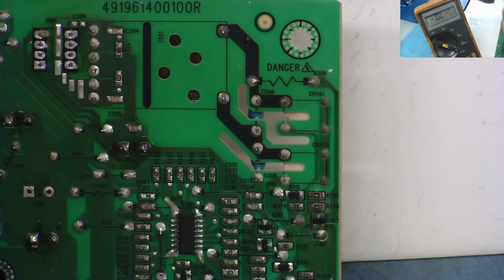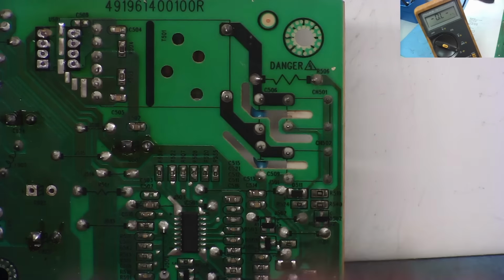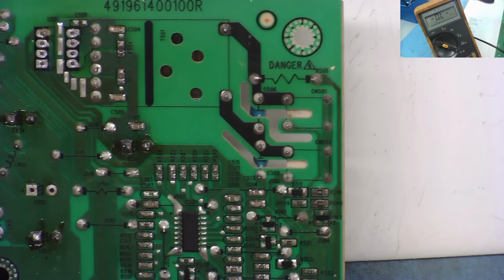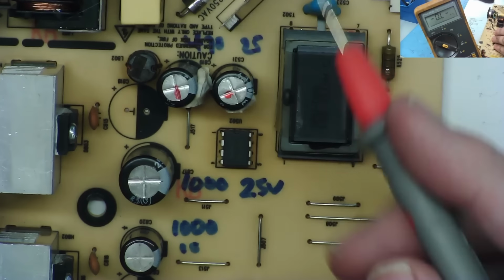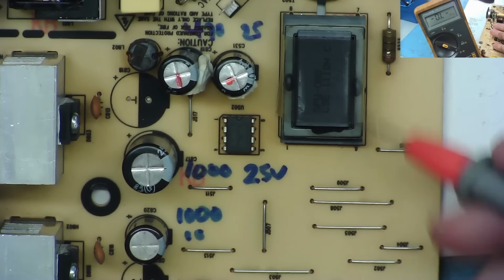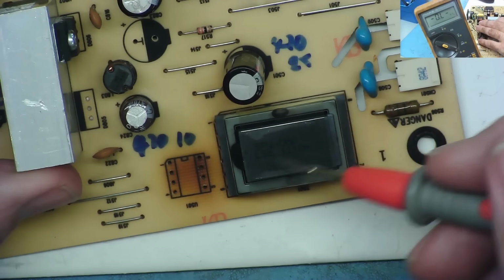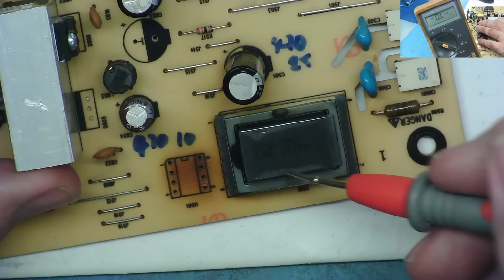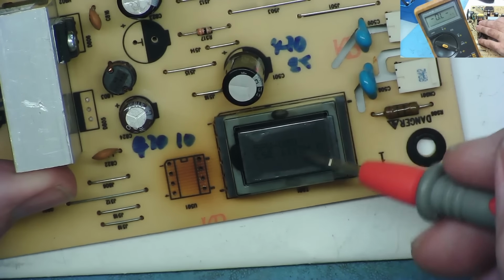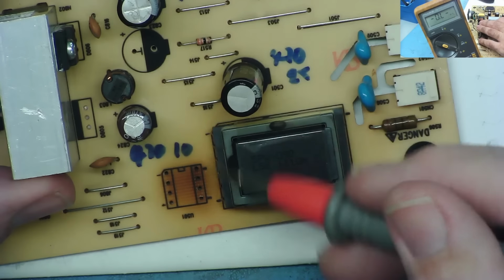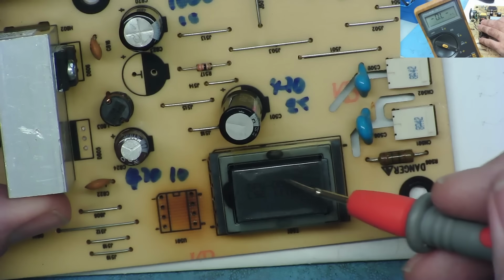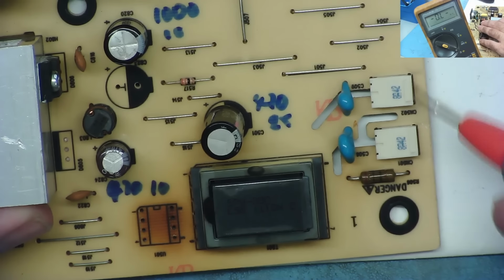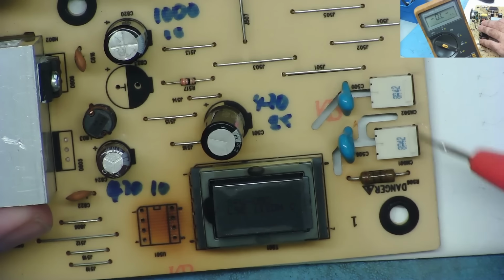We could use the low ohms meter, but I'm pretty confident that both of these transformers are okay. And the other reason, apart from the fact they read basically the same as each other, is that if you've got a shorted turn or something in one of these, the thing is going to look distressed - it's likely to burn up or overheat, and I'm sure you'd see some signs of stress if that was actually faulty, or anything on the secondary.